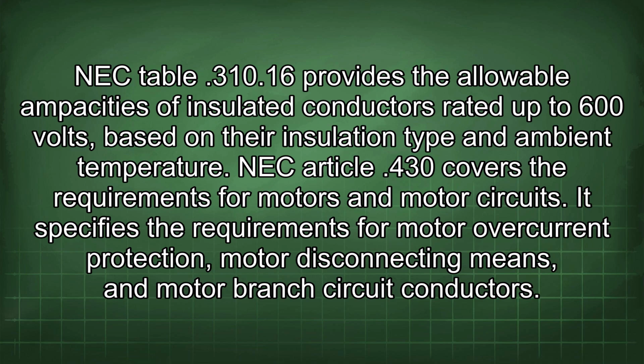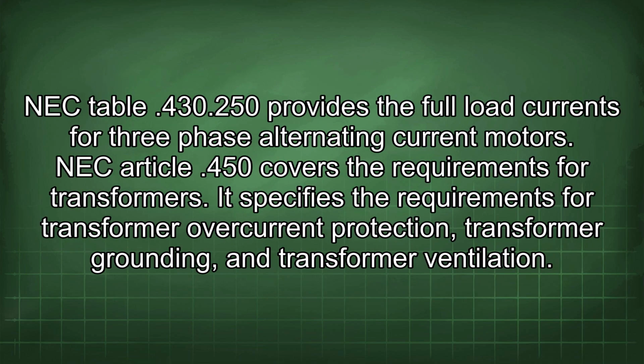It specifies the requirements for motor overcurrent protection, motor disconnecting means, and motor branch circuit conductors. NEC Table 430.250 provides the full load currents for three-phase alternating current motors. NEC Article 450 covers the requirements for transformers. It specifies the requirements for transformer overcurrent protection, transformer grounding, and transformer ventilation.